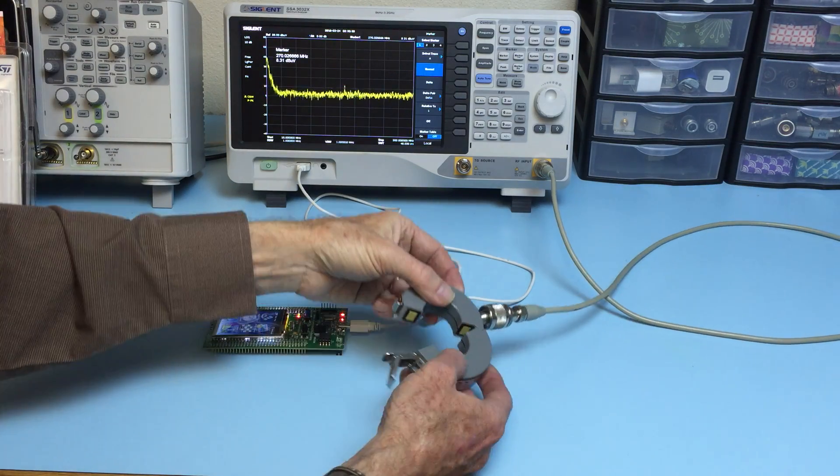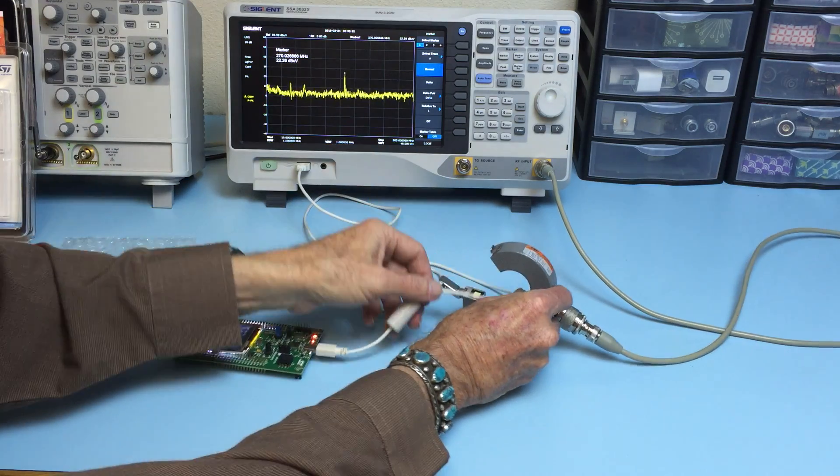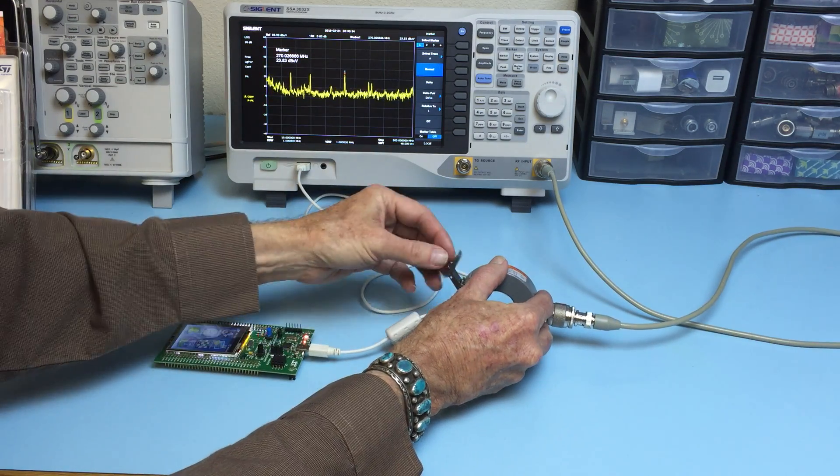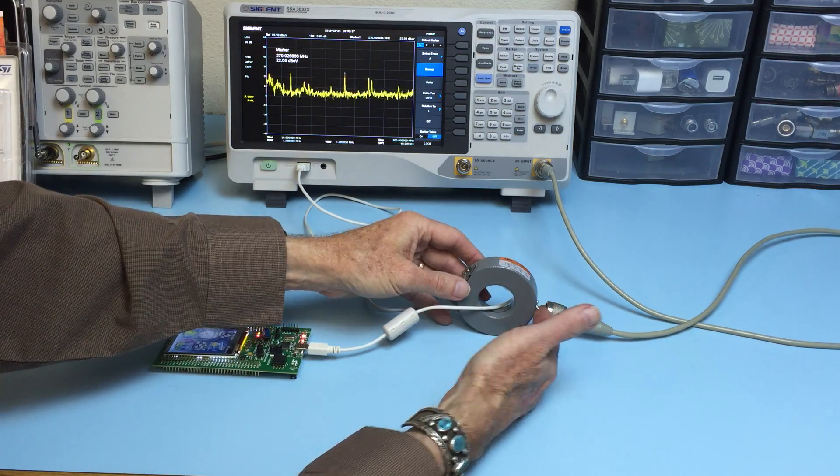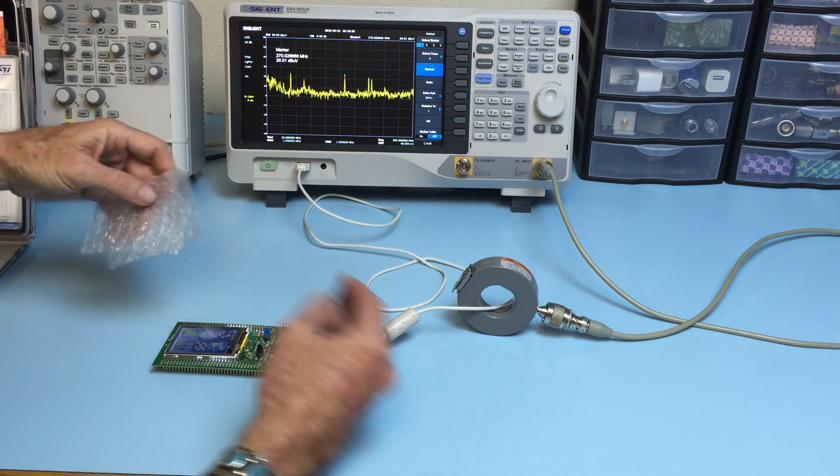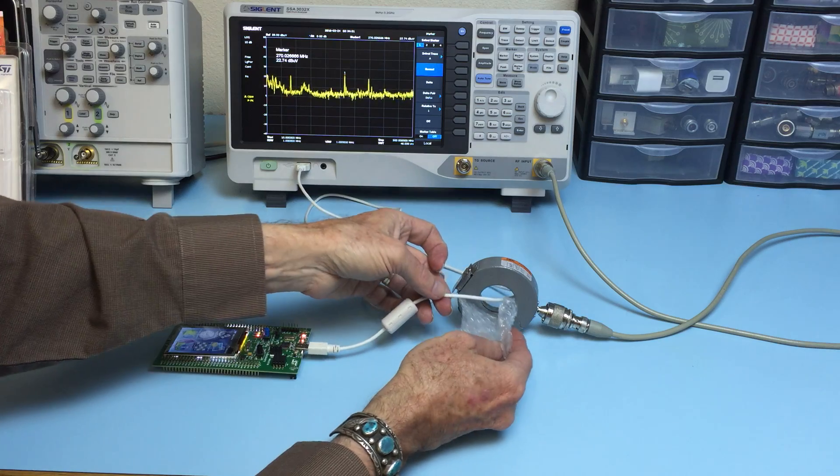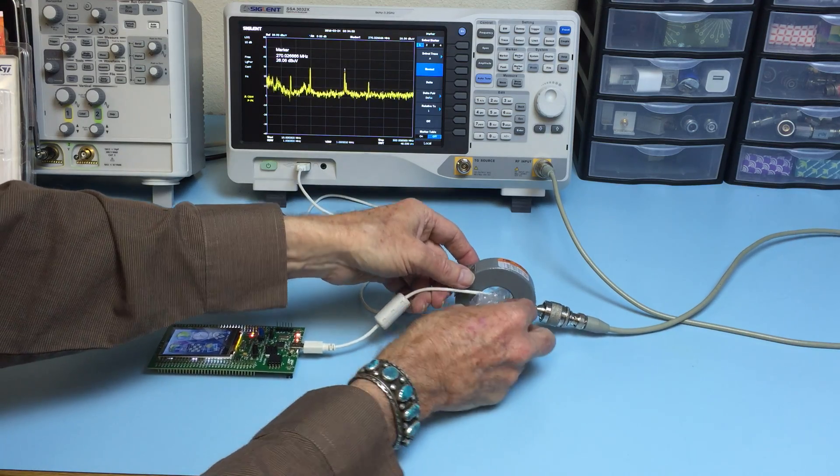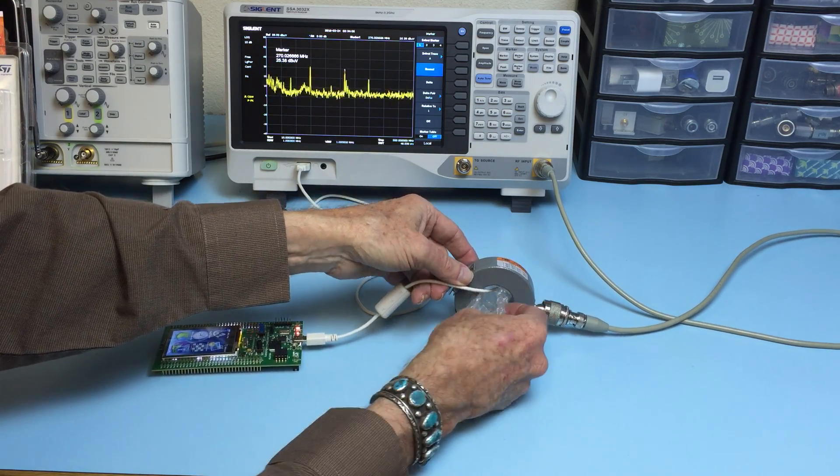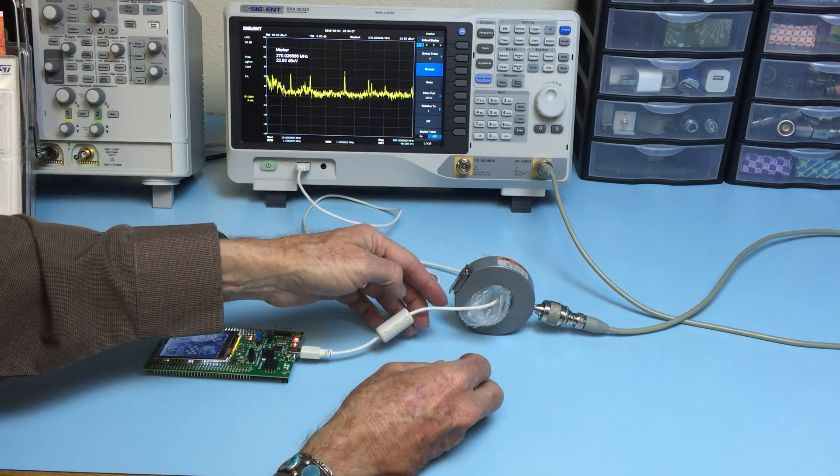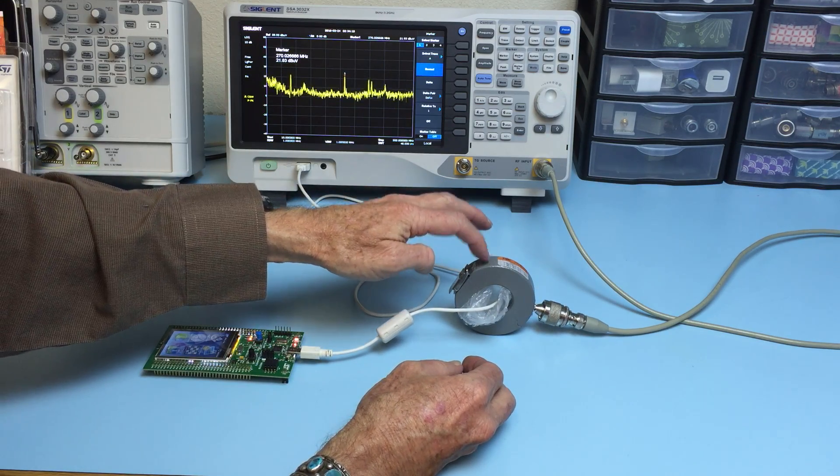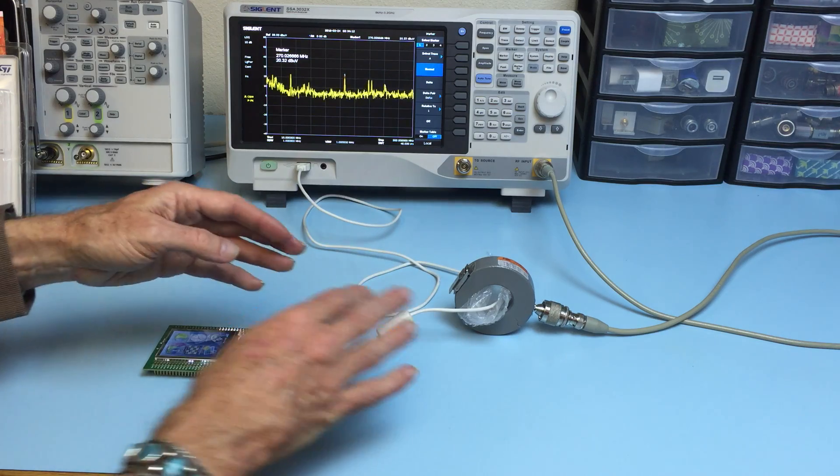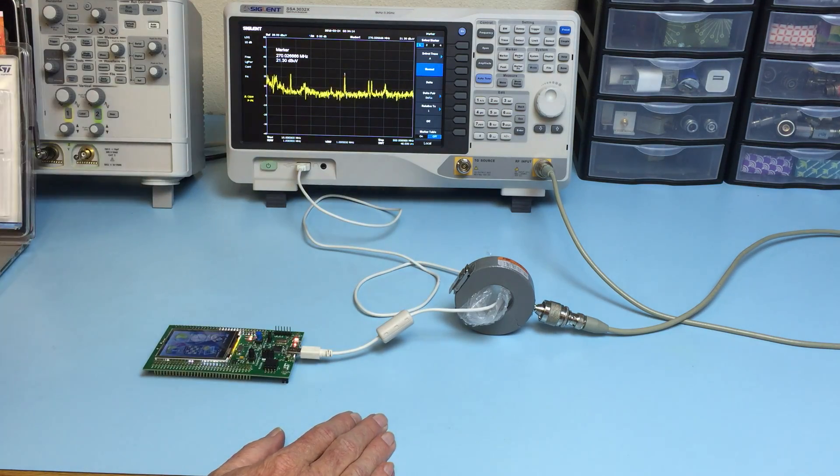What you do is clamp this around the cable like so. I usually use a little bit of bubble wrap to keep the cable as much in the center as you can, because if the cable touches the metal case here, it can affect your measurement.